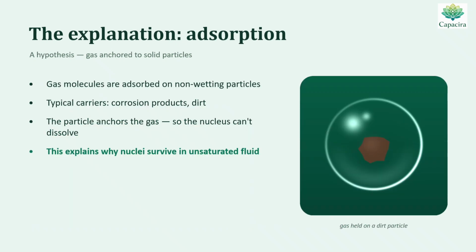This is the expected explanation. The tiny gas bubble is usually not floating freely. Instead, it is attached to microscopic solid particles. These particles may be dirt, rust, corrosion product, tiny mineral particles or other non-wetting impurities. The gas molecules stick to these particles by a phenomenon called adsorption.